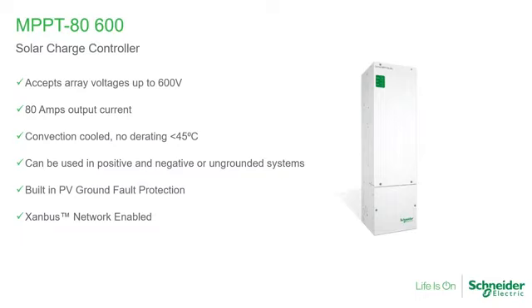The output is 80 amps. Out to the batteries, it will be 80 amps. And remember, this is a DC to DC device, right? So it takes the higher voltage from the array and steps it down to the battery voltage. And the battery voltage for this product can be 24 or 48. It will auto detect on commissioning if it's connected to a 48 volt battery or if it's connected to a 24 volt battery. So you can buy the same product for different systems.